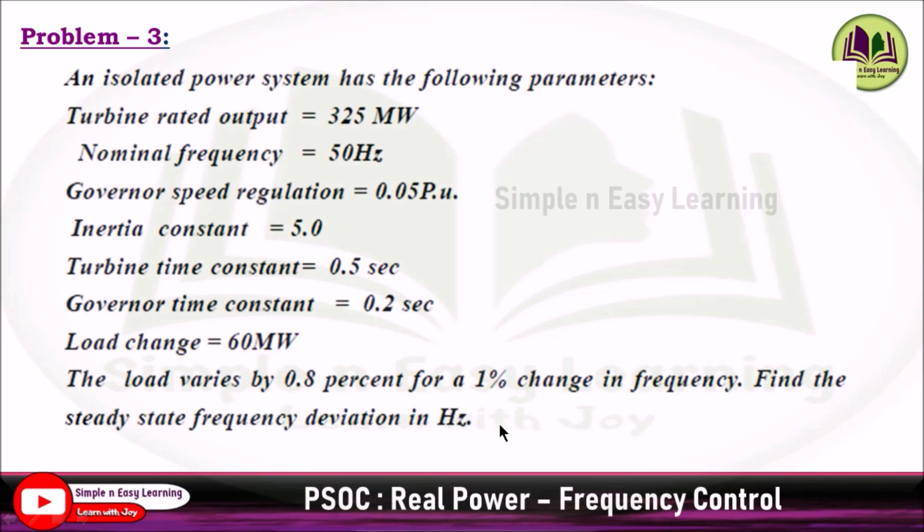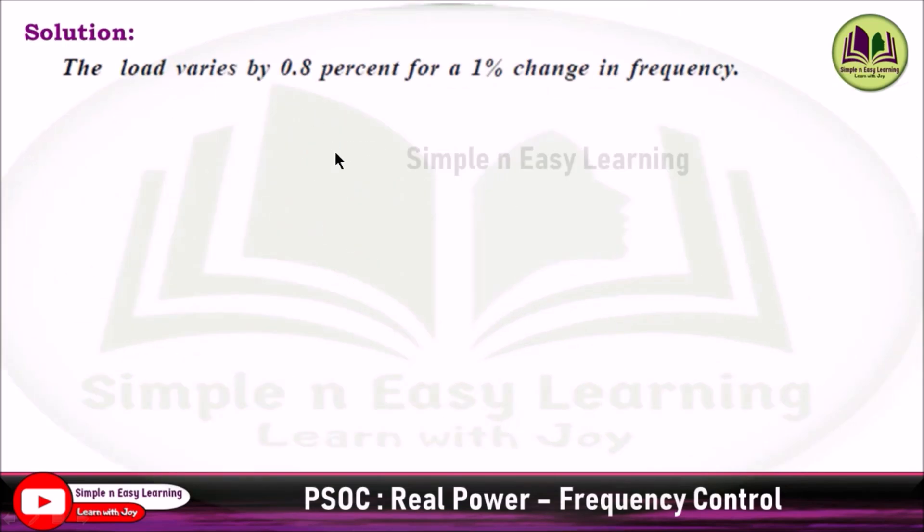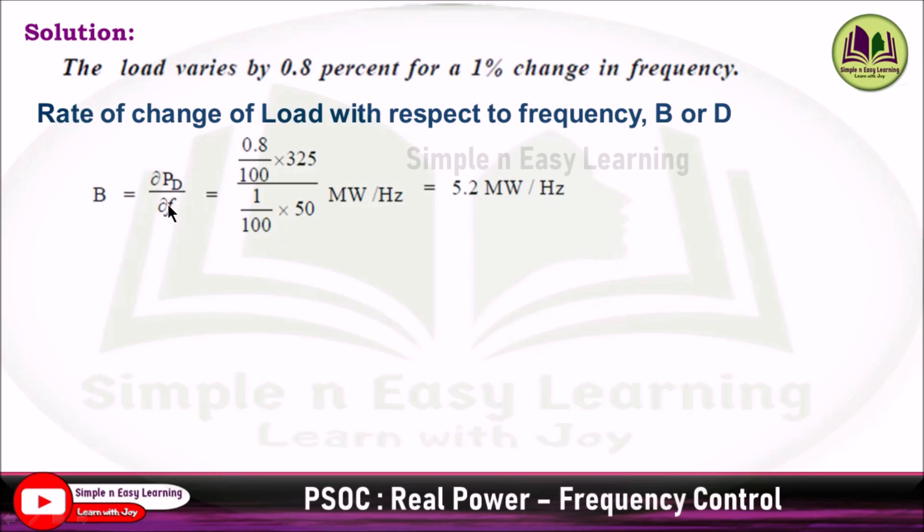Solution: The load varies by 0.8 percent for a 1 percent change in frequency. The rate of change of load with respect to frequency, B or D, equals ΔPd/Δf. So 0.8 divided by 100 times 325 megawatt, divided by 1 by 100 times 50, gives you 5.2 megawatt per hertz. In per unit divided by the base power, 5.2 divided by 325 gives 0.016 per unit megawatt per hertz.